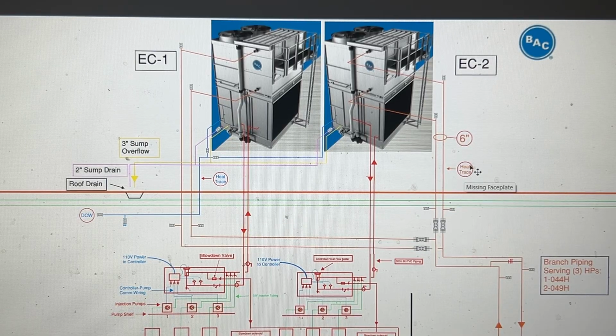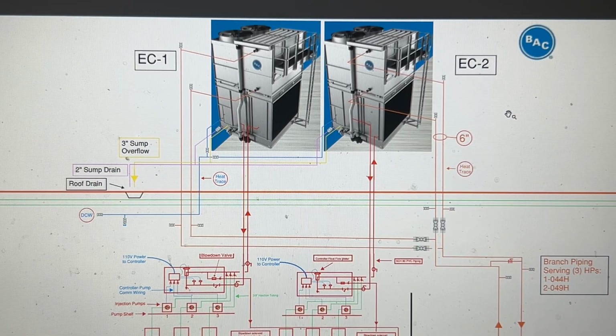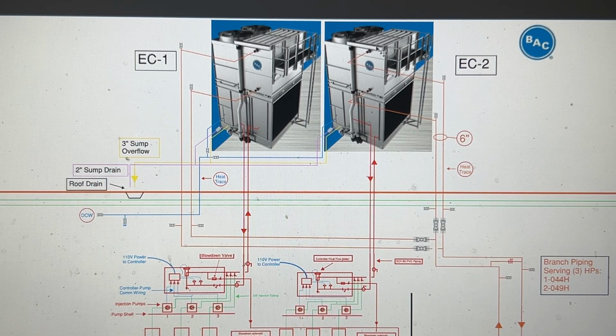So how this works is when we need cooling for the system, the cooling towers act as that cooling property. Basically, they cycle that flow of water through the coil here, and what happens is that there is a sump full of water at the lower portion of this cooling tower. This pump takes that water, shoots it up this riser, and there's a series of sprayers here that spray down. These are counterflows, not crossflow. So what that means is crossflow would be this direction going through. Counterflow is up and down.